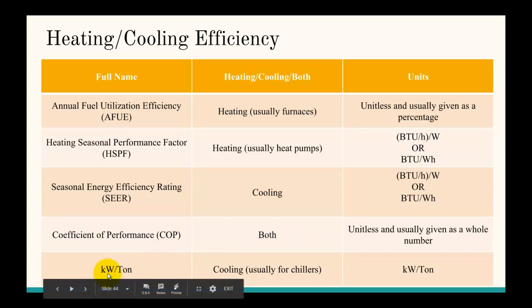Last but not least, kilowatt per ton. This is usually for chillers, and the weird part is this is the only unit here where you have the input power, which is in kilowatts, over the output. So it's not really an efficiency per se, but more of a performance measurement. You have to be really careful when using kilowatts per ton that you put the input energy in kilowatts over the output energy in tons. Okay, so now let's get to the problems.